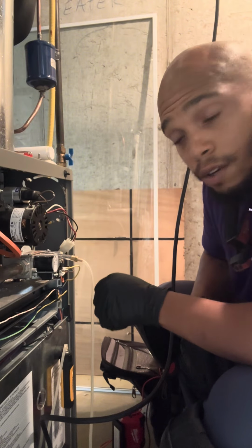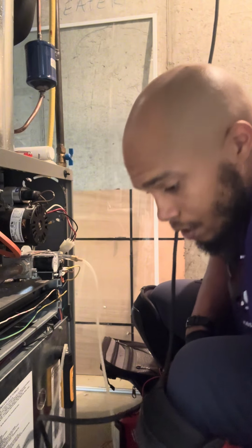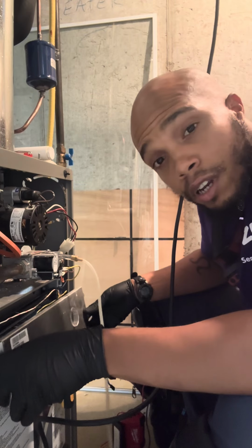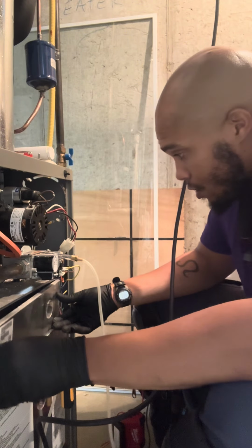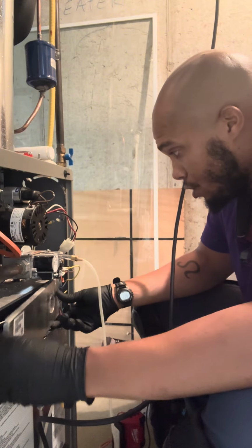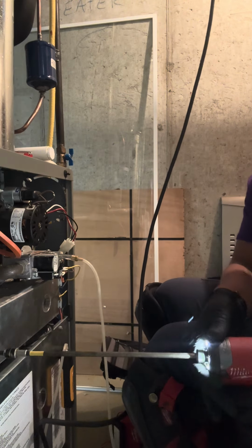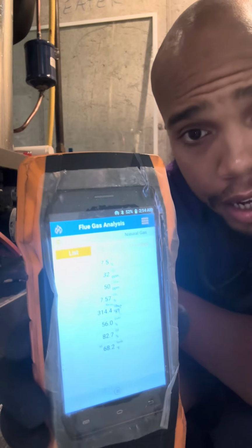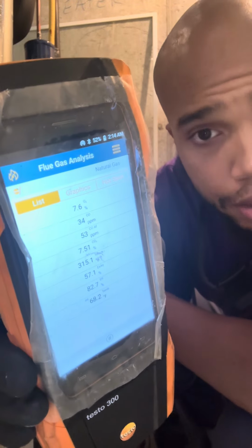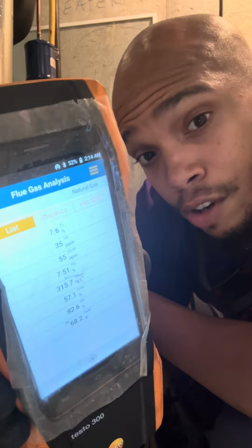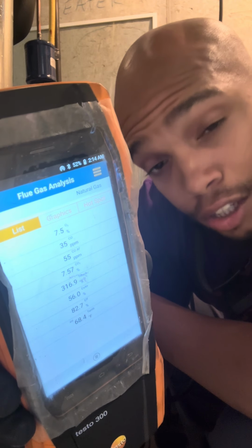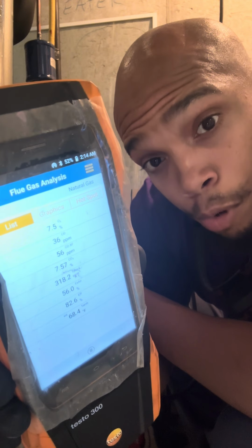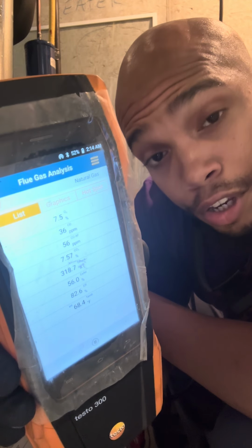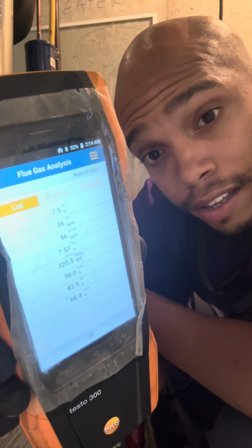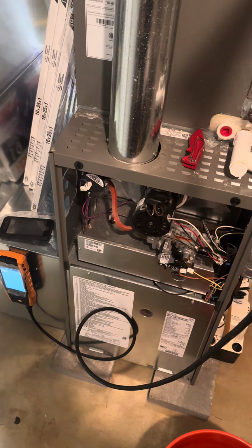All right, so we've got the system running. We've checked the flames. I'm going to now close the door. Let this system run for a good 20 to 30 minutes just to make sure that no sneaky issues persist. So far, this is my combustion test. I don't know if you can see it, but these are the numbers that I need to read to make sure that everything is going right with your system. I need to check your oxygen levels, your carbon dioxide levels, most importantly, your carbon monoxide levels. I need to see your efficiency and your excess air to make sure that this thing is getting enough air for combustion. The system has been running for 25 minutes now, and all of my pressures are looking good.